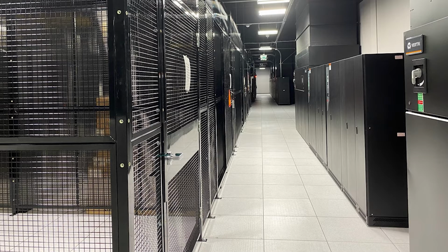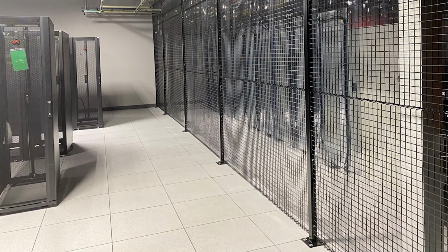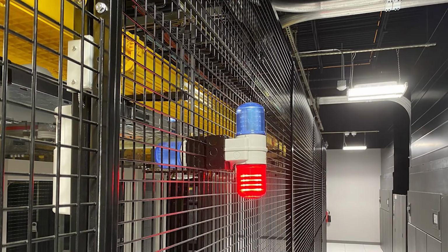Server lifts and crash carts are provided in each data hall for customer use. The second row of cabinets are configured with hot aisle containment. They are equipped with a solid back door and chimney, which controls the flow of the hot air and forces it into the return plenum space so it cannot mix with the cold air in the room. This is a very efficient design, allowing loads up to 34 kilowatts per cabinet. The limiting factor is the fans in our equipment. They must be able to move a lot of air to achieve 34 kilowatts of actual draw in the cabinet.